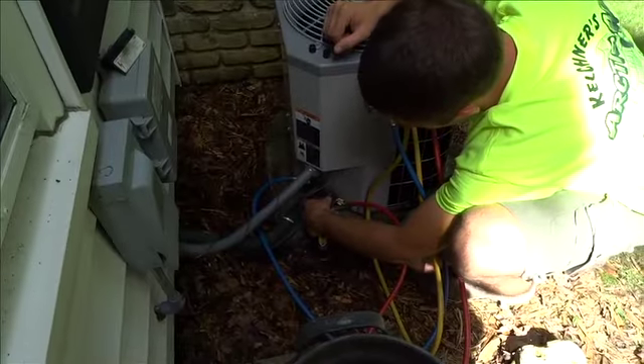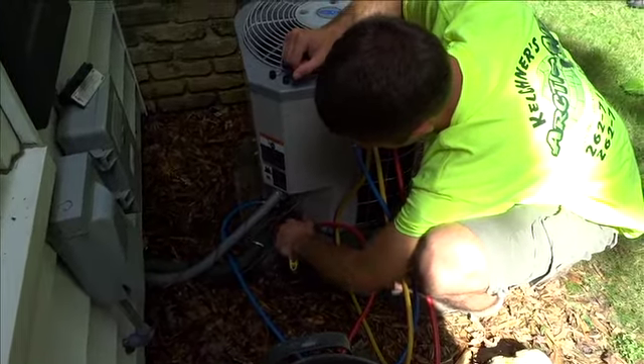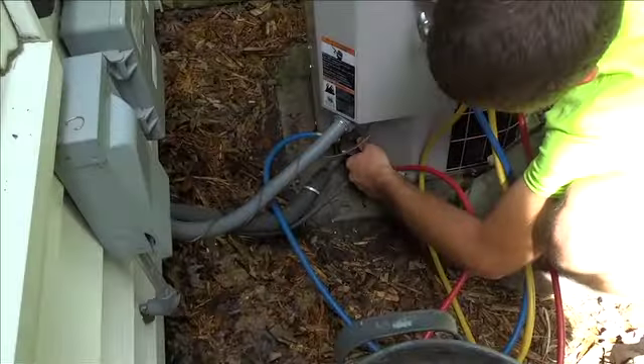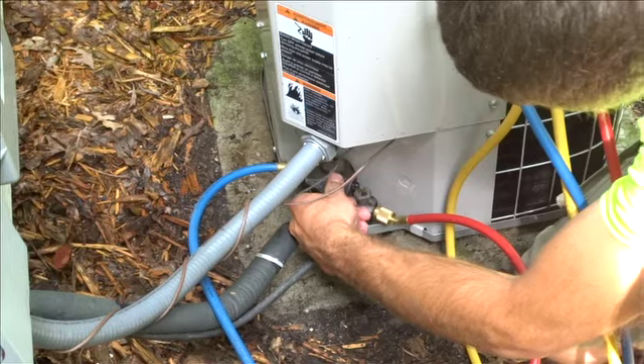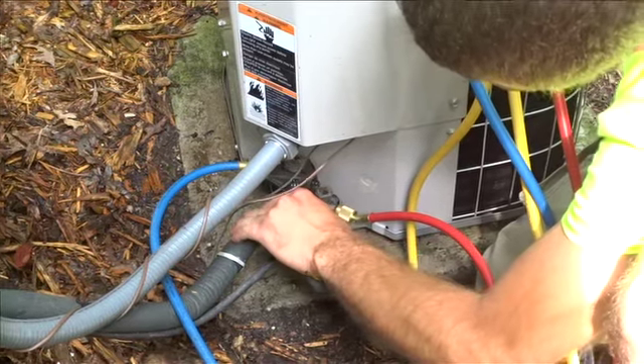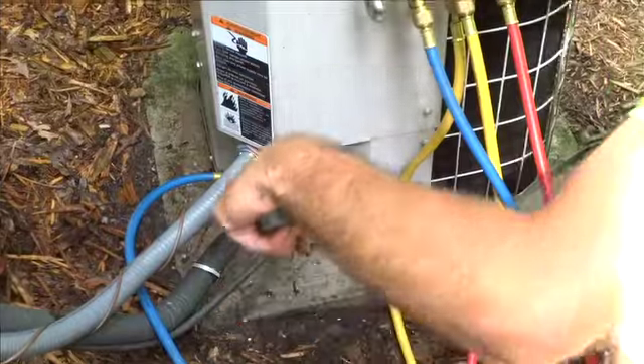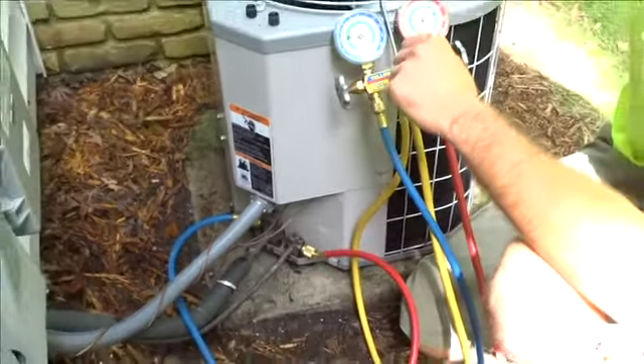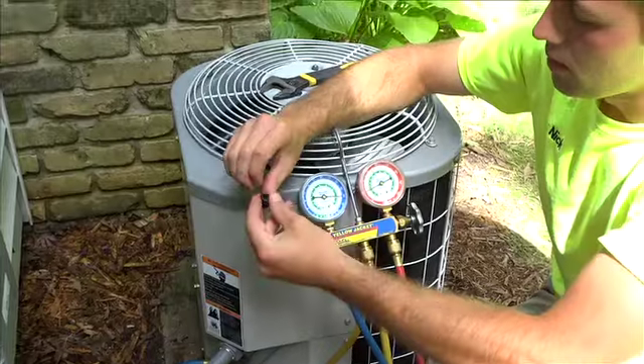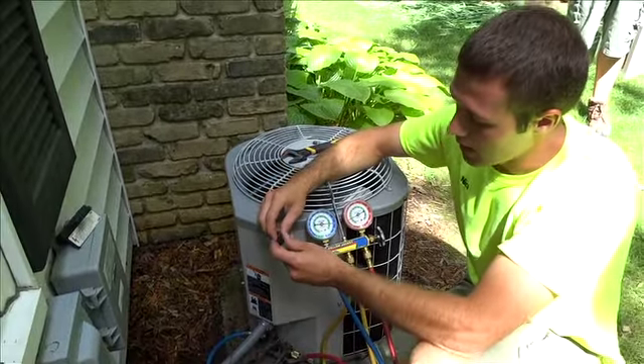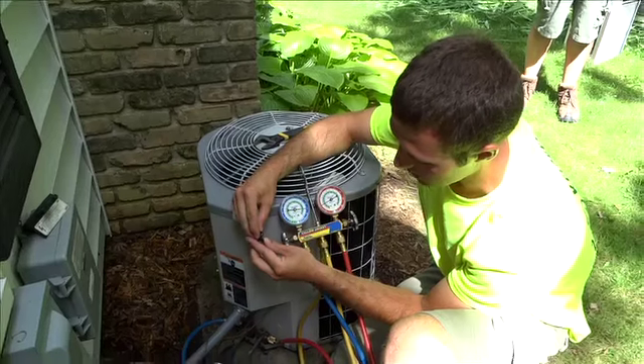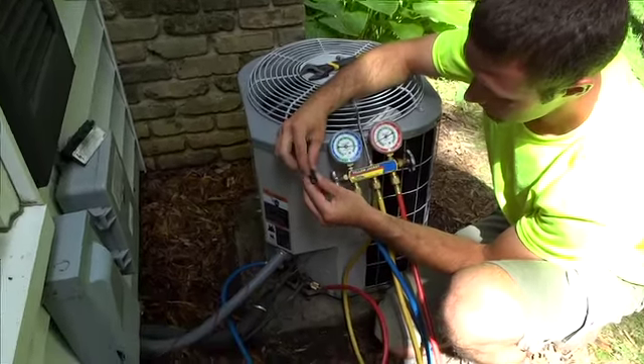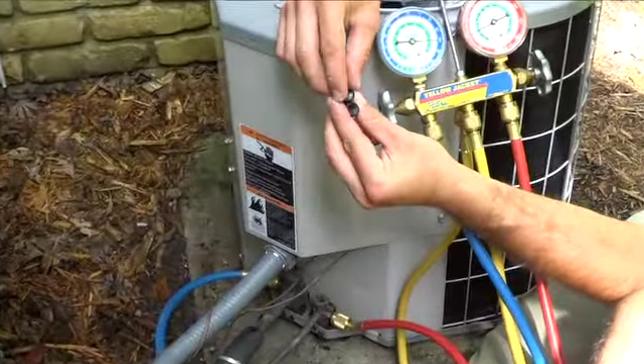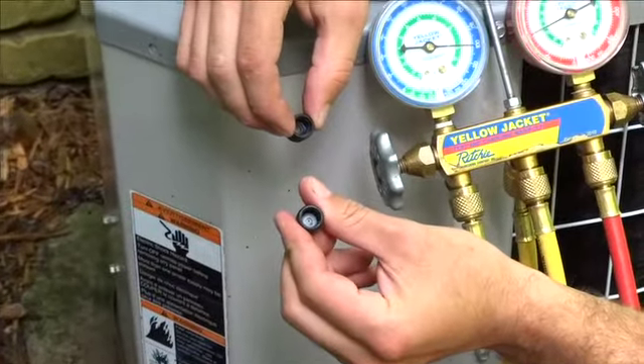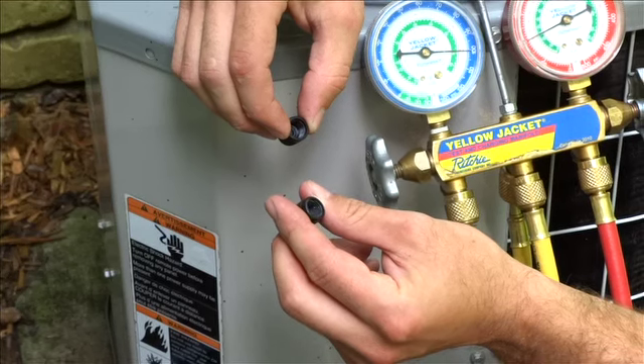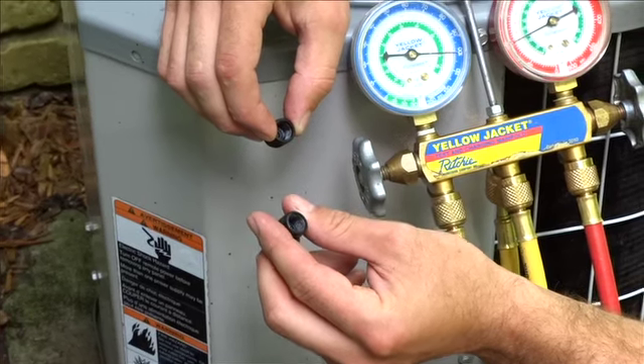Another thing that we like to check, just make sure these service caps are tight. Just one place Freon can escape from. When they're installed, they should be tightened down, which these are tight and good to go. And before I hooked up my gauges, they have caps to block the refrigerant from coming out. They all have O-rings in them. One of your O-rings was missing, so that's another place refrigerant can escape from.